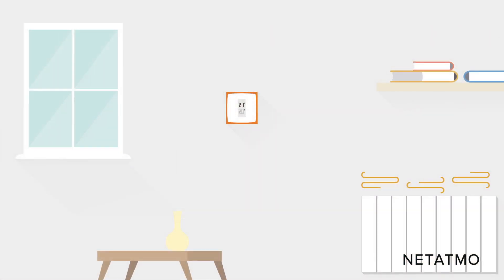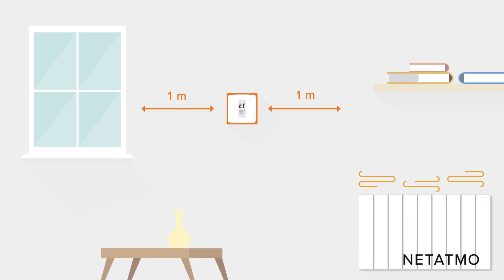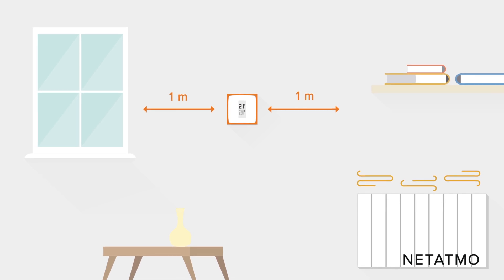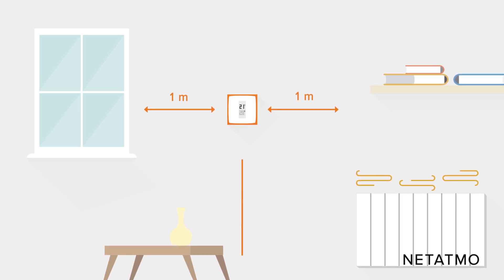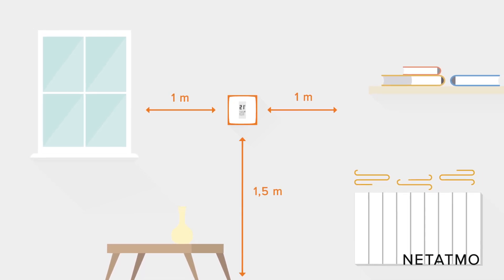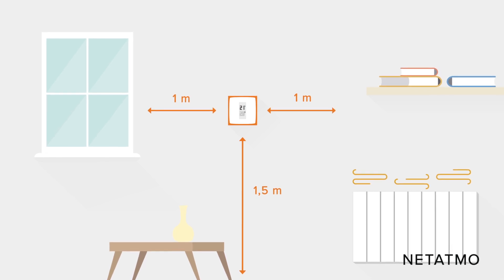The thermostat needs to be placed at least one meter away from any cold or heat source, such as any openings or radiators, and approximately 1.5 meters off the ground.